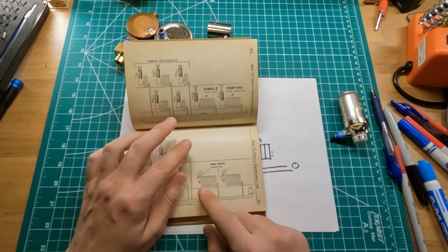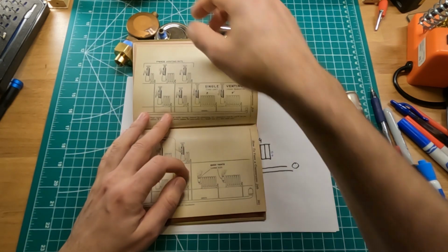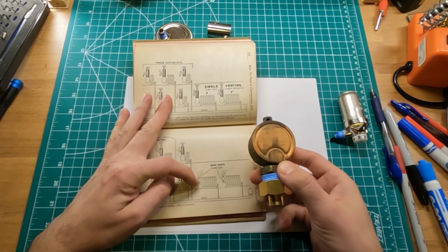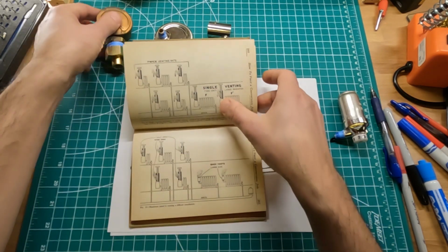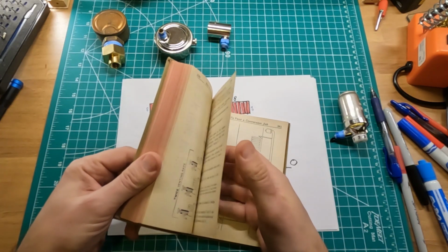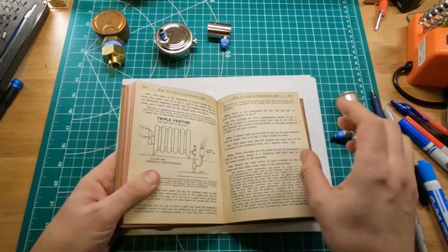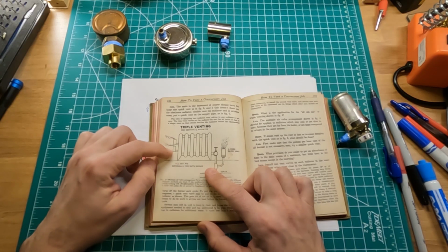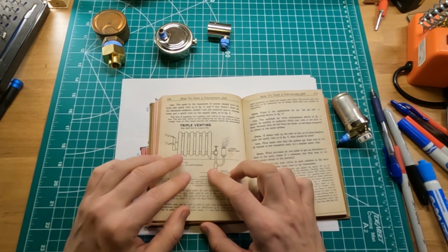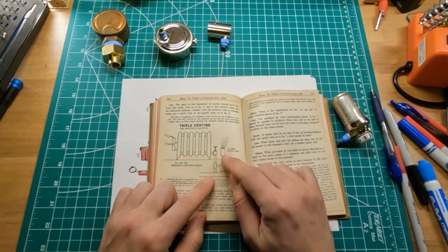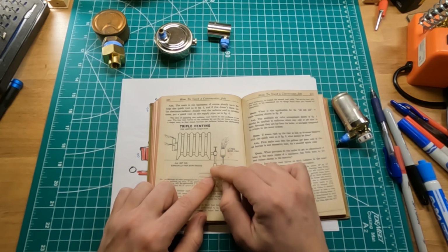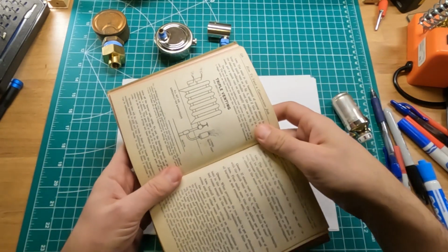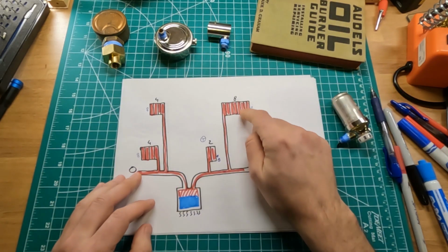Here in this example, he's tapping to a larger radiator, so in other words, he's adding this main vent to the large radiator. That's a possible solution. And there's yet another solution. Let me just really quickly, there you go, something like this. That means not only do you have double vents on this oversized radiator, he's also adding another vent on the supply pipe to the radiator. So those are possible solutions for this oversized radiator.